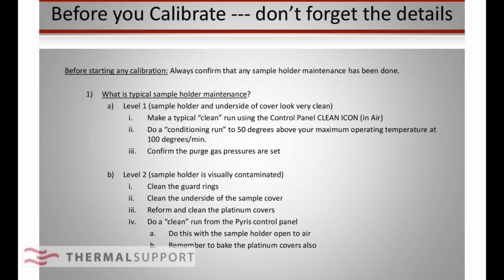So I went in and did a complete sample holder maintenance routine on this. Got it looking good again, so it looked just like it used to look, and reran the performance verification. It was dead on. There was no need to go any further than that. So don't forget the details. When you do your sample holder maintenance, there's a couple of different levels. One is, if you're one of those customers that is blessed with a simple sample, everything's clean, you've got that perfect scenario that everybody likes, and you've decided that your performance verification has failed and you want to recalibrate, the first thing you do is do that level 1 maintenance.